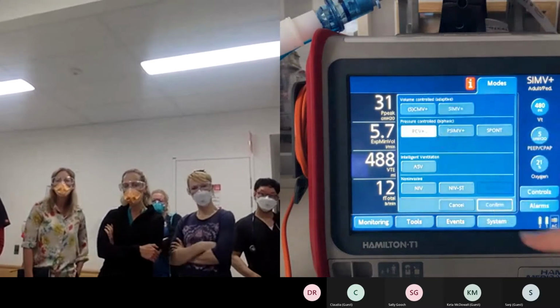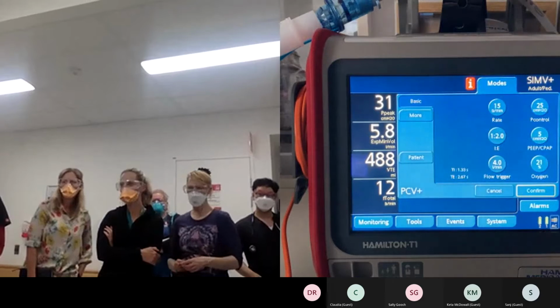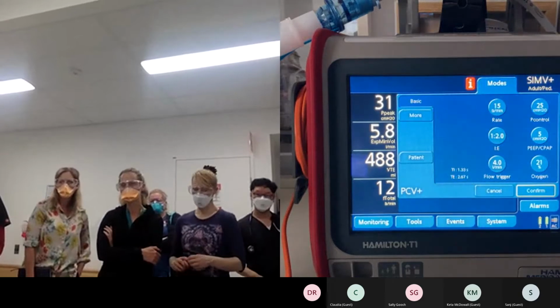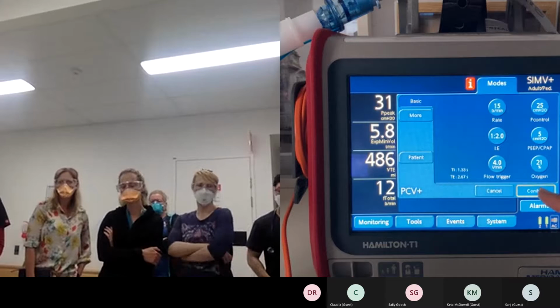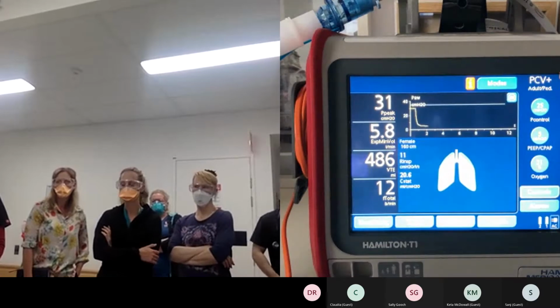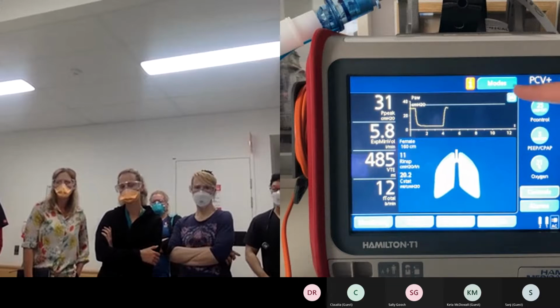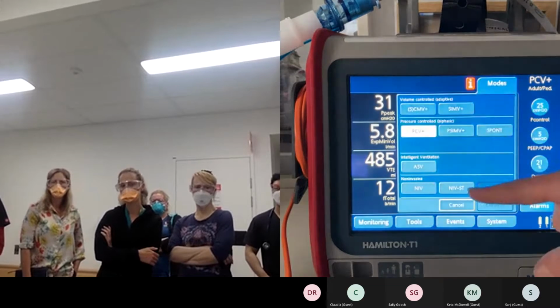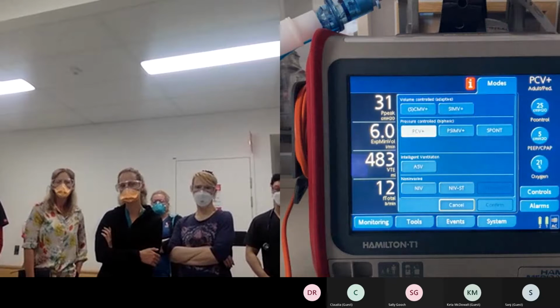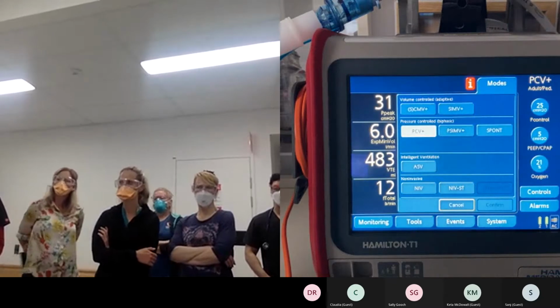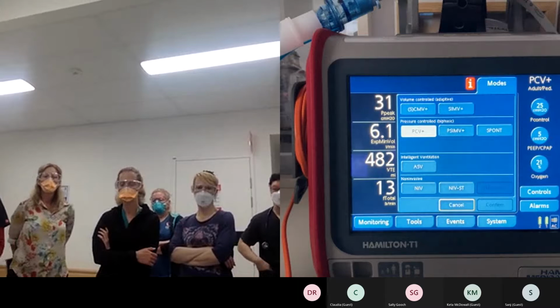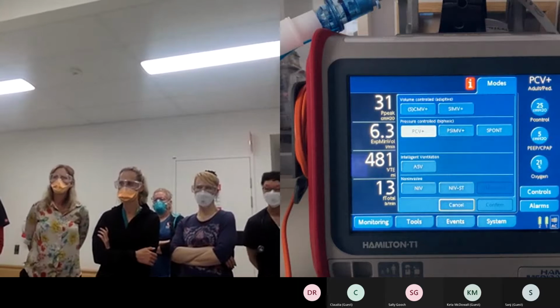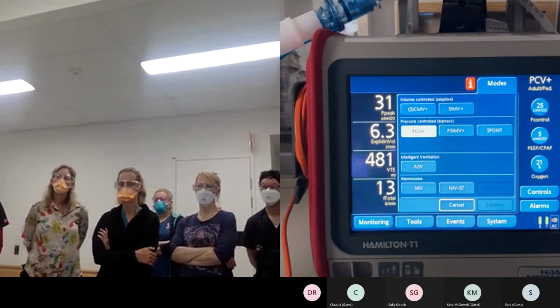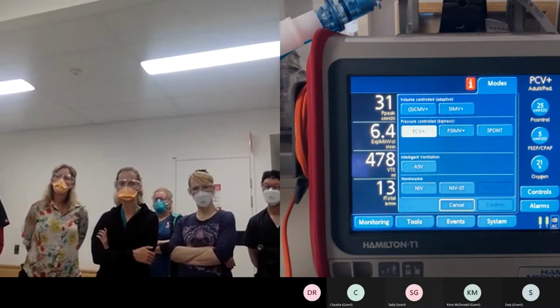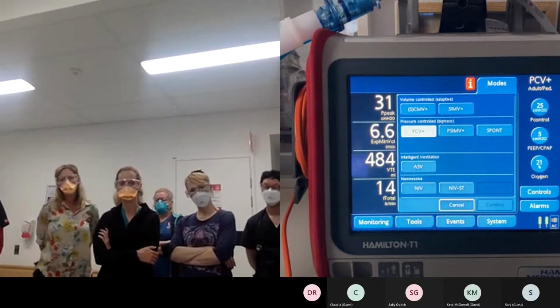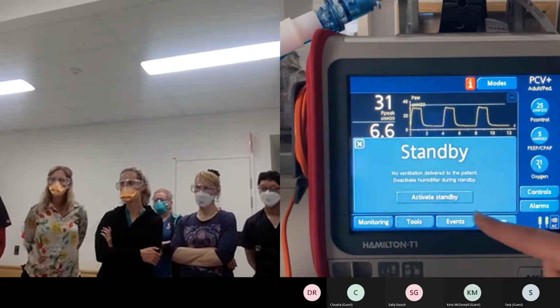If you want to change mode, so let's say you want to move over to a pressure mode, you're still delivering in this mode, you're setting up in this mode. It's not until you hit confirm that you move over. Okay, but you can see when you come into modes, you can move between non-invasive and invasive without going into standby, but you can't move into high flow. The reason is that you need to move into a wet circuit to do high flow, and you can take the flow sensor out.